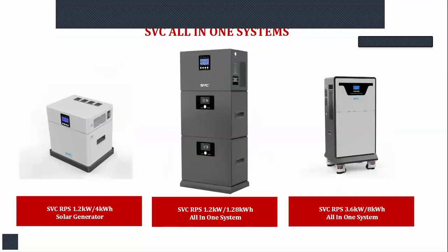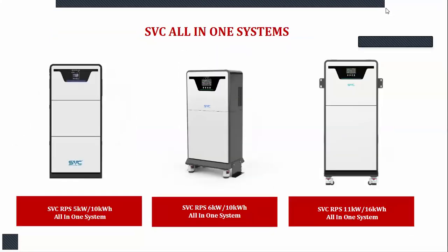Now let's see the SVC all-in-one system. All-in-one, as the name implies, means it's like a standalone system with the batteries connected directly. For some, you don't even need a cable, just a link. For this one, you just need a short link provided by the manufacturer, so you don't need external battery cable or external battery breaker. All you need to do is bring your solar cable, your input grid, and your load cable into it.